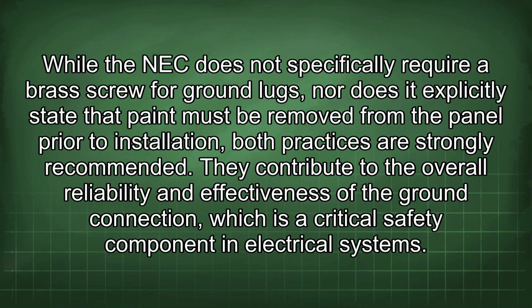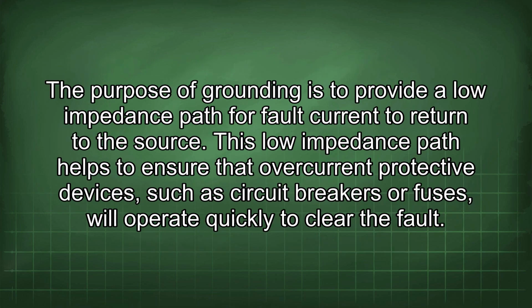While the NEC does not specifically require a brass screw for ground lugs, nor does it explicitly state that paint must be removed from the panel prior to installation, both practices are strongly recommended. They contribute to the overall reliability and effectiveness of the ground connection, which is a critical safety component in electrical systems. The purpose of grounding is to provide a low impedance path for fault current to return to the source.